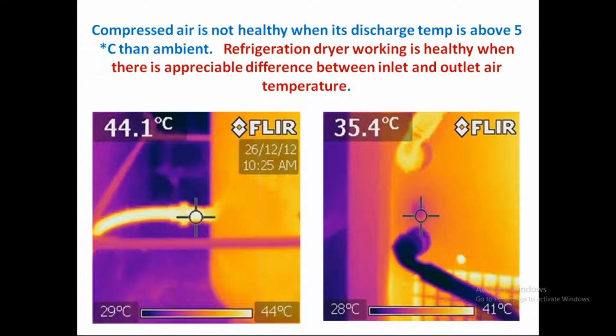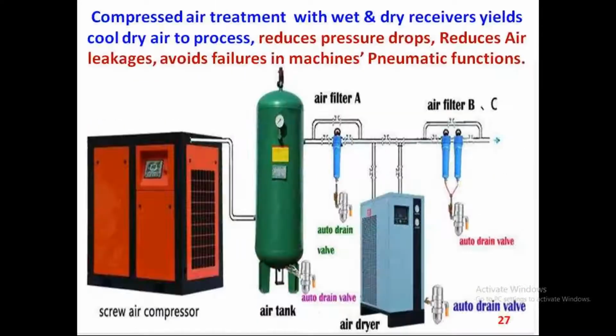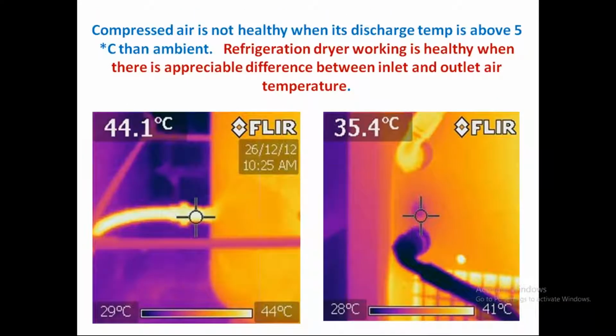Any dryer for the given process, as I was telling you, this is the dryer used. It's a 1000 CFM compressor, which means the dryer minimum those days, one decade back, they were using a 1000 CFM dryer. But now the pressure drop across the dryer is going up, so they are going for a 1300 CFM dryer. Why this 1300 CFM dryer is needed is, when the temperature of the air inlet from the receiver to the dryer goes to 44 degrees, straight away the dryer gets derated by 10 to 20%.